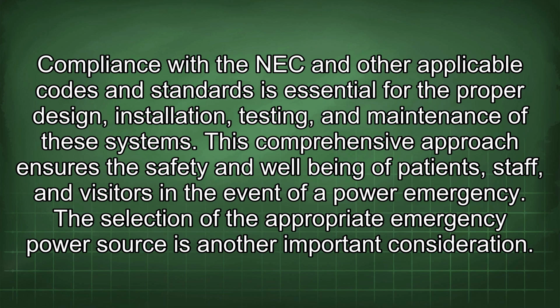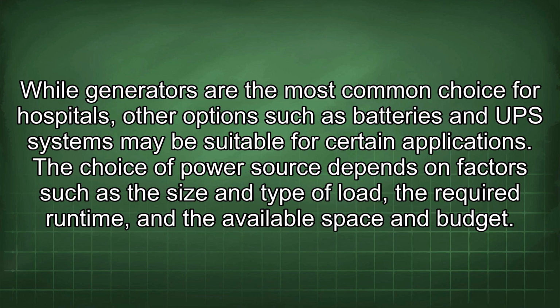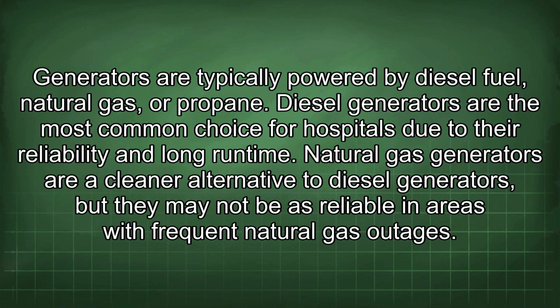The selection of the appropriate emergency power source is another important consideration. While generators are the most common choice for hospitals, other options such as batteries and UPS systems may be suitable for certain applications. The choice of power source depends on factors such as the size and type of load, the required runtime, and the available space and budget. Generators are typically powered by diesel fuel, natural gas, or propane. Diesel generators are the most common choice for hospitals due to their reliability and long runtime.